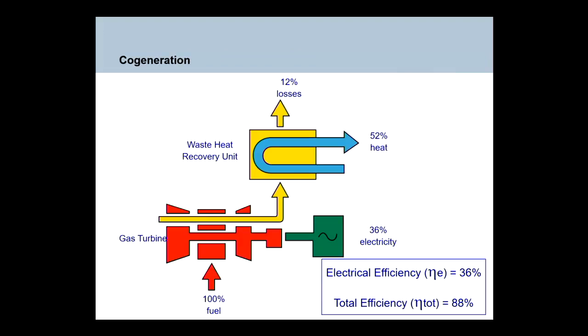And then the other option is cogeneration. Not so common in Australia, quite common in Europe and North America, where you have a gas turbine which produces electricity, but the exhaust of the gas turbine is used for some type of waste heat recovery. So typically, if you have a factory that needs heat, this sort of system is used quite a lot because the factory can then generate its own electricity, and the waste heat from the gas turbine, much lower grade waste heat, is then used in the factory process.